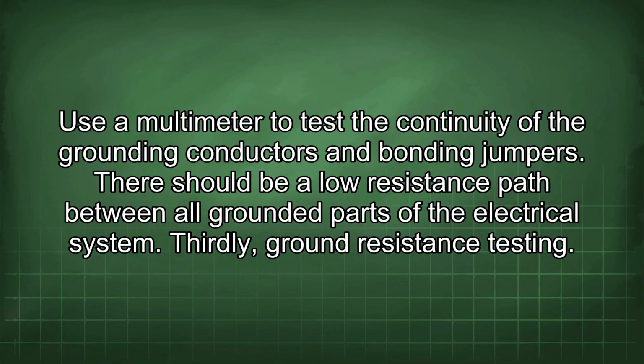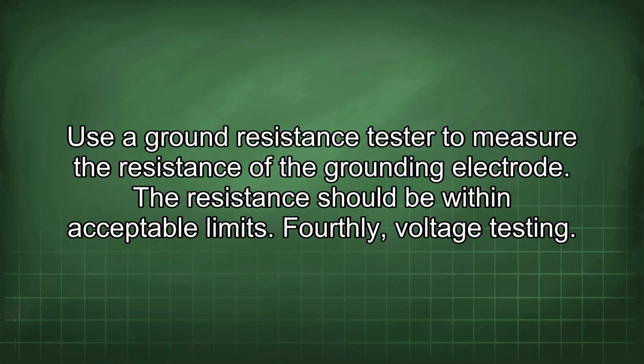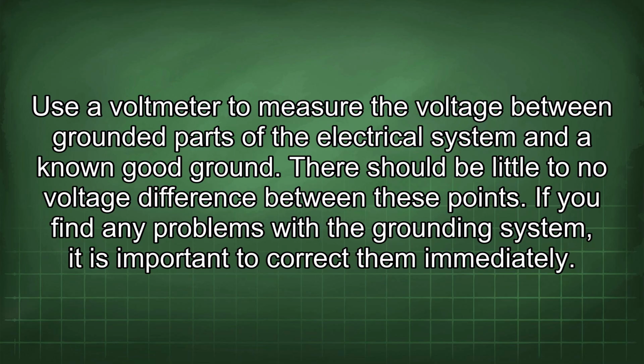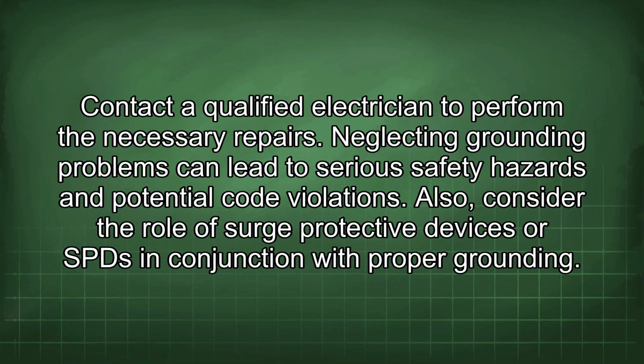Thirdly, ground resistance testing. Use a ground resistance tester to measure the resistance of the grounding electrode. The resistance should be within acceptable limits. Fourthly, voltage testing. Use a voltmeter to measure the voltage between grounded parts of the electrical system and a known good ground. There should be little to no voltage difference between these points. If you find any problems with the grounding system, it is important to correct them immediately. Contact a qualified electrician to perform the necessary repairs. Neglecting grounding problems can lead to serious safety hazards and potential code violations.